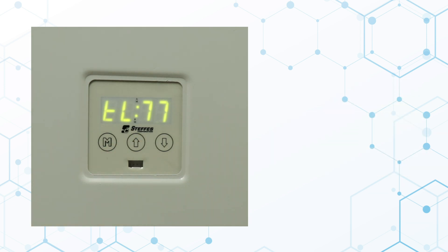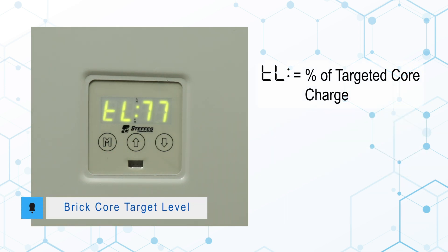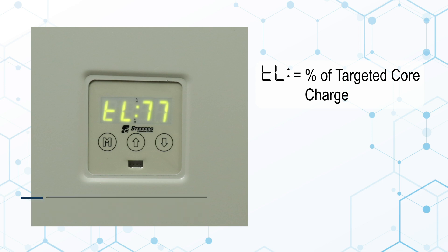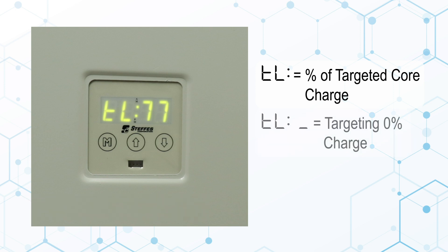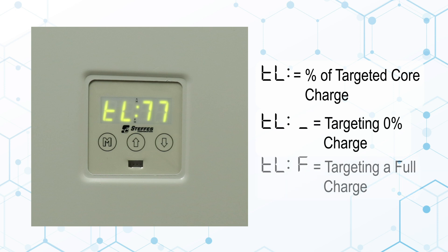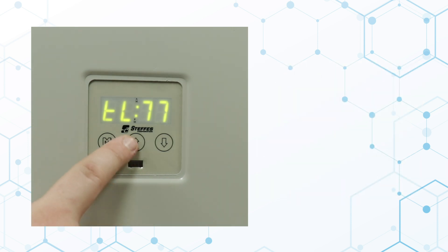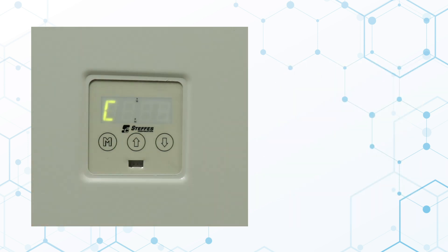Press the up arrow once more, and the display will show TL and a number, indicating the current percentage of brick core charge targeted by the forced air system. TL underscore indicates the system is not targeting any heat in the brick core, and TLF indicates a full core charge target level. Press the up arrow again to return to the normal operating display.